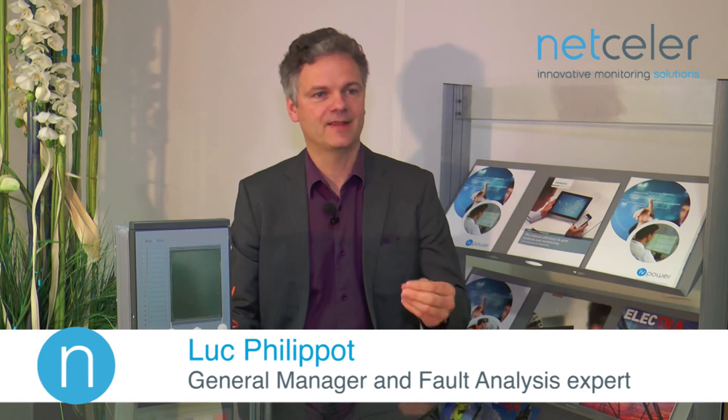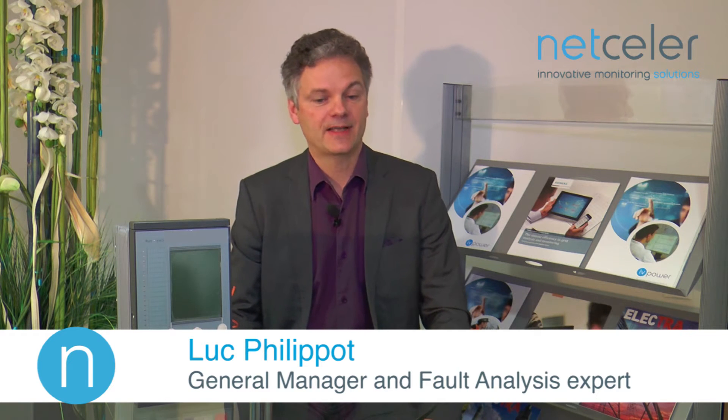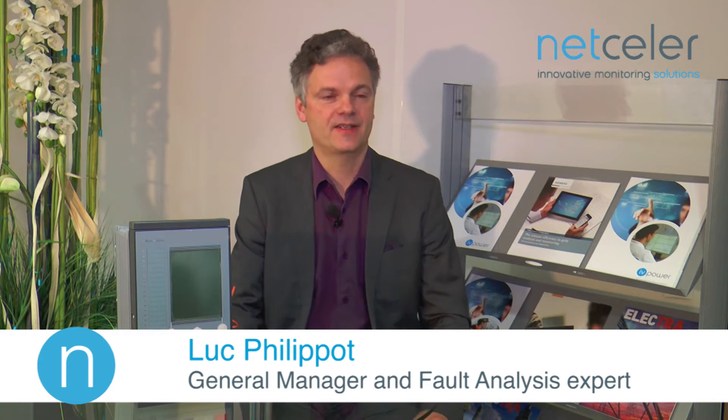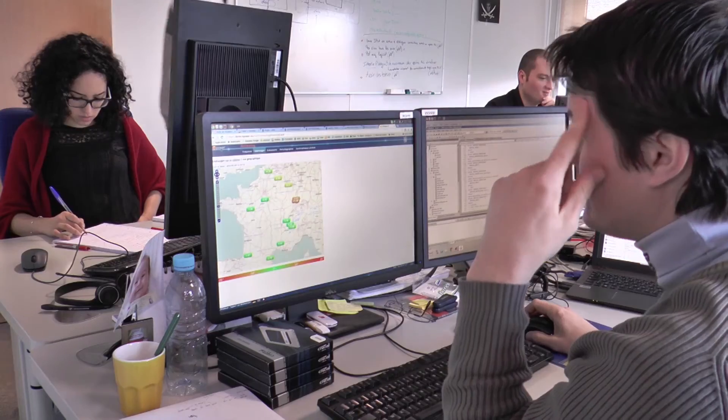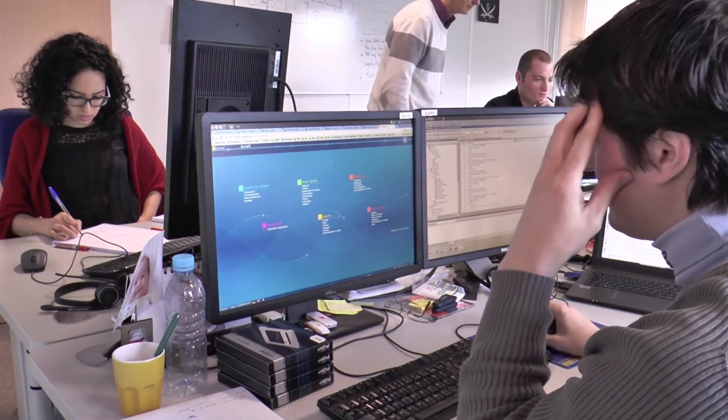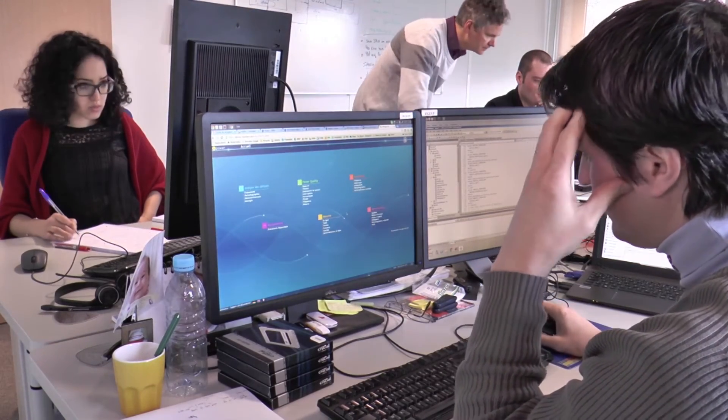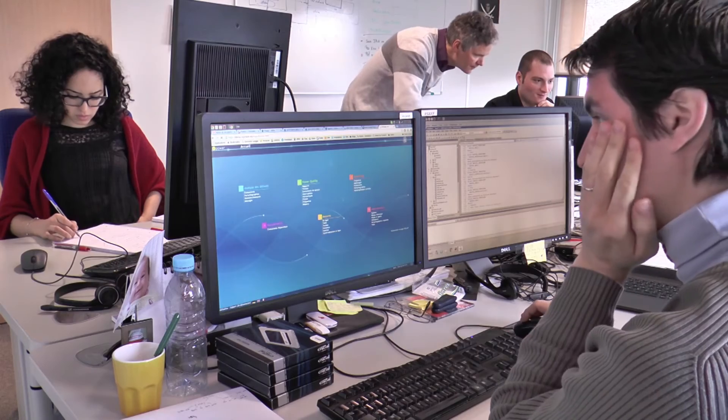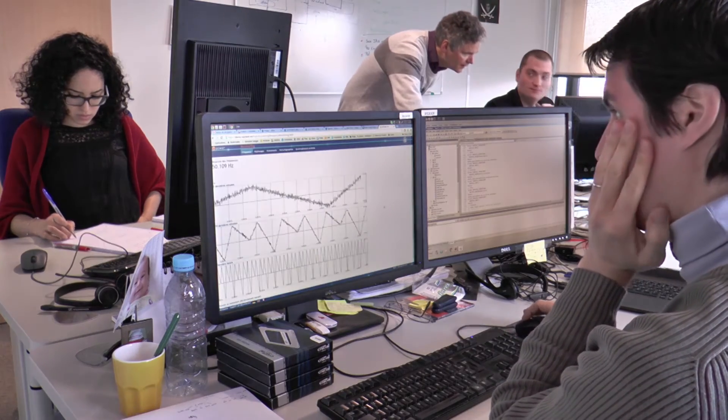Automated fault analysis is a technology that will make use of digital data from the field. The kinds of data we are able to process are essentially disturbance records, either from protection relays or digital fault recorders like this one, but also event logs from substation automation systems or from sequence of event recorders, and additionally event-related data like lightning strikes.